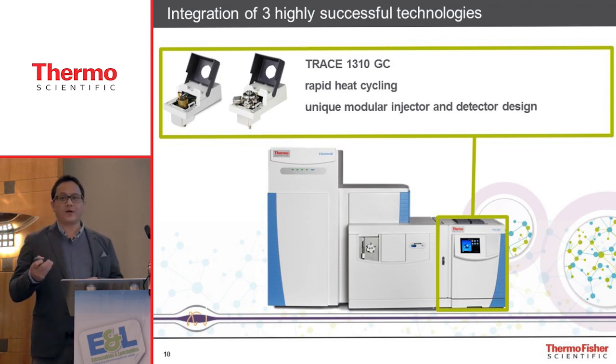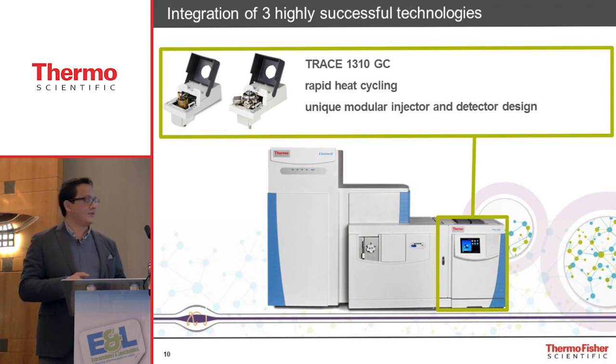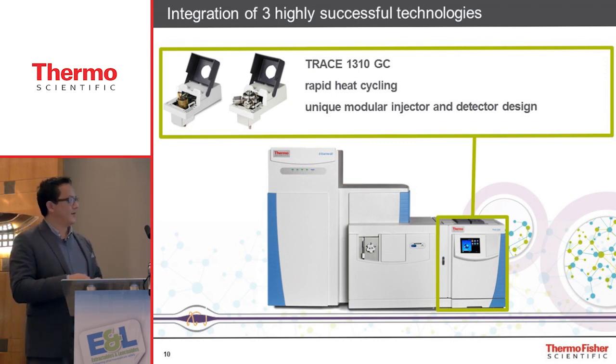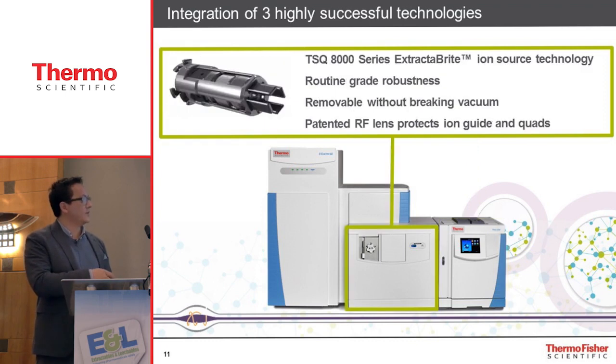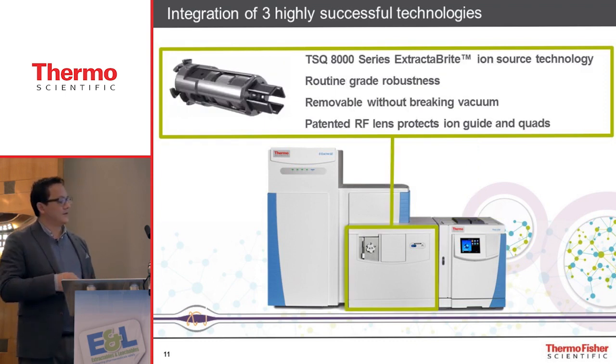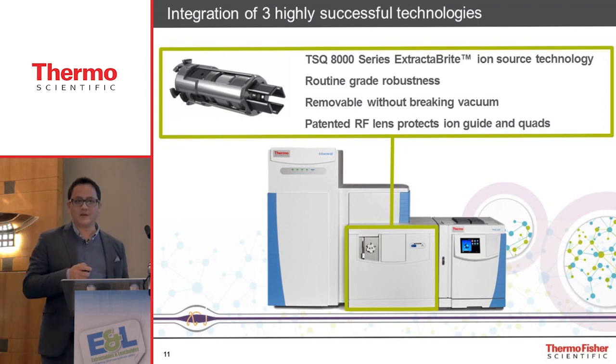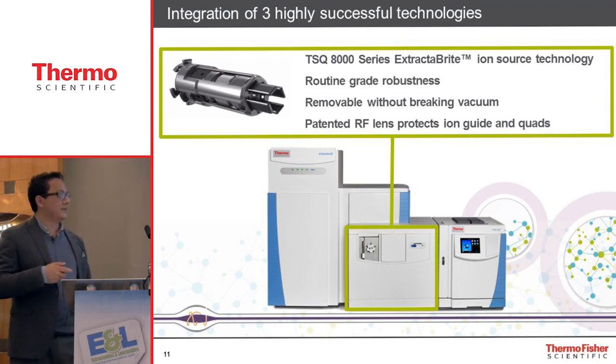So what is the system? Well, it comprises three key established robust technologies that we brought together almost like Frankenstein into one nice package. And we have an established GC system, a truly modular system that allows multiple different injector modules to be dropped into the top, headspace, programmed temperature vaporization, so on, all that great tech that people know and love. And then behind that we have an ionization source that we developed for environmental analysis, actually, people who wanted to run robust sediments for weeks on end without ever having to clean their instrument.